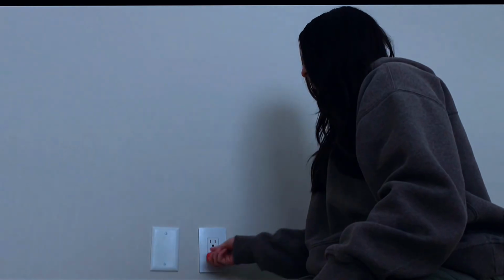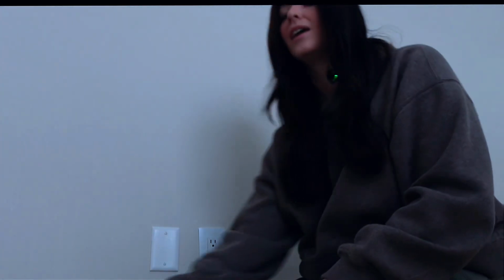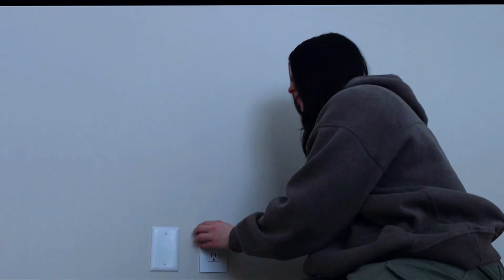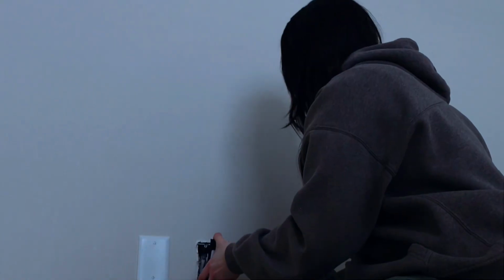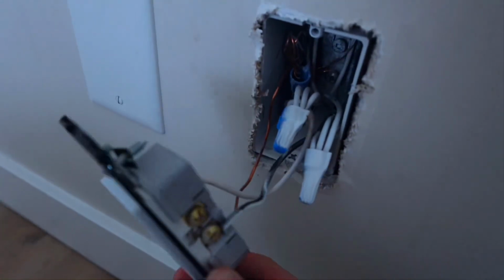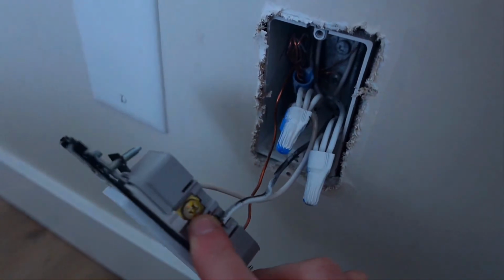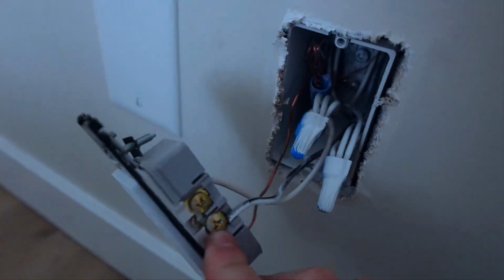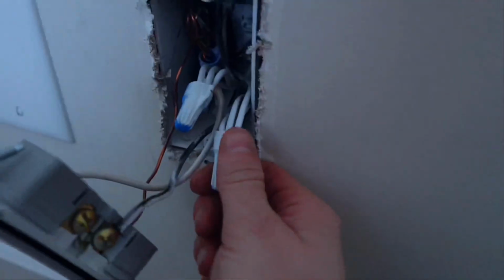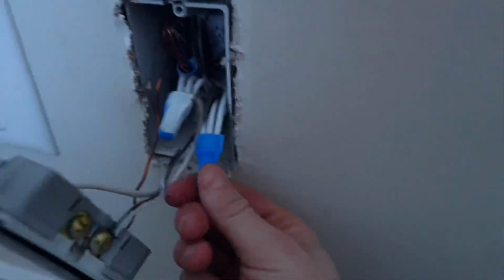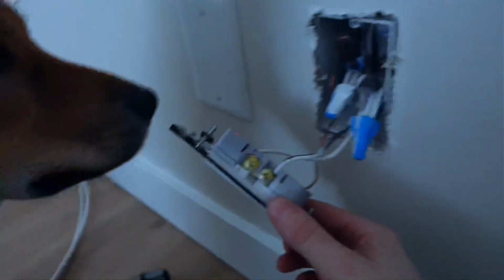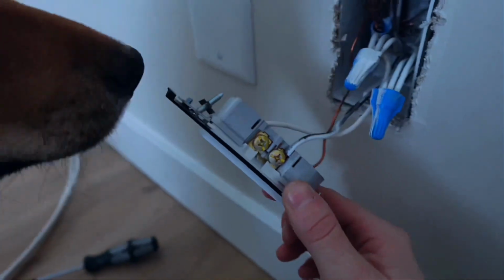All right, so now that the power is killed to the receptacle, let's pull this plug apart. A lot of you guys are gonna pull apart your receptacle and you're going to see both wires going to each screw of the receptacle. This plug was done correctly here because, as you can see, they spliced the wires together with a pigtail going to the receptacle. Unfortunately, in a lot of cases, the receptacle is being used as the splice.